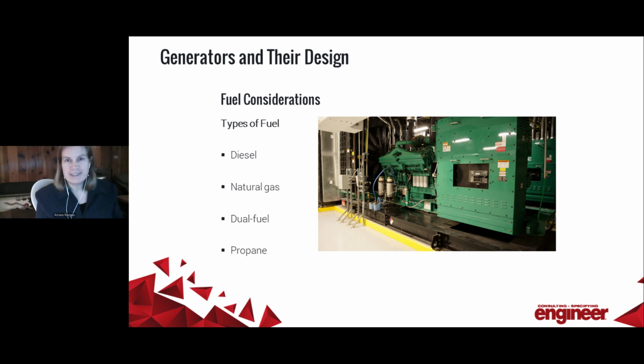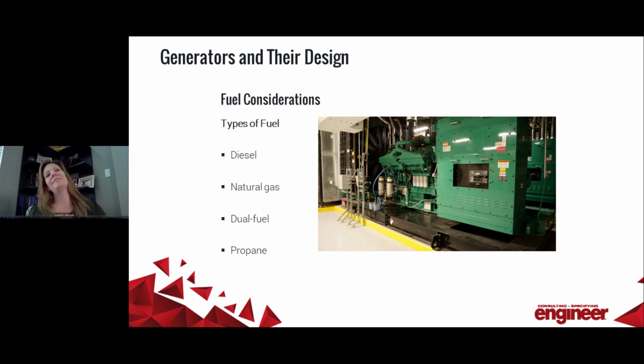What's next? All right. Well, Amara, the results of that poll are definitely not surprising because, as we noted earlier in this presentation, the bulk of the people on this call are designing systems to support critical loads such as hospitals, right? And for these types of facilities, diesel is by far the most popular fuel choice. However, it's not the only kind. So when it comes to types of fuel, we've got many options. We've got diesel, we have natural gas, we have dual fuel, which is a combination of diesel and natural gas, and we even have propane.